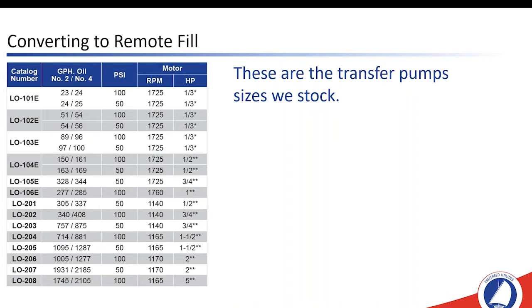And then if a 100 PSI pump isn't going to do it, take a look at your line sizing. The output from the Preferred web app tells you your friction losses through the pipe, through the valves, and your vertical hydrostatic pressure too. So if you're doing a system that's 10 floors or less and you're seeing 100 PSI discharge, your piping is probably undersized. And the same is true too. If you're doing a system that's all on the same level and you're seeing a discharge pressure more than 50 pounds, then your piping is probably undersized, because the vertical just isn't that much.